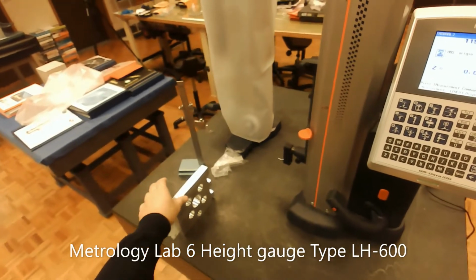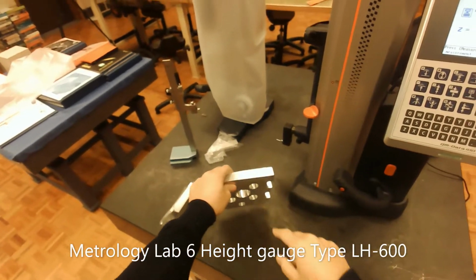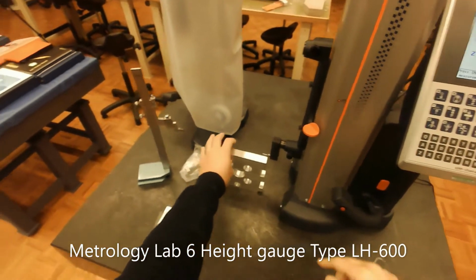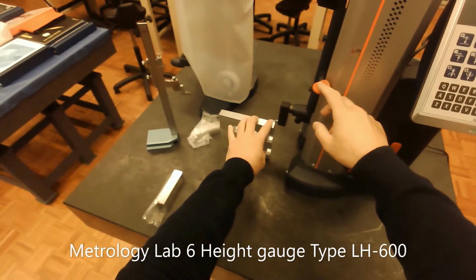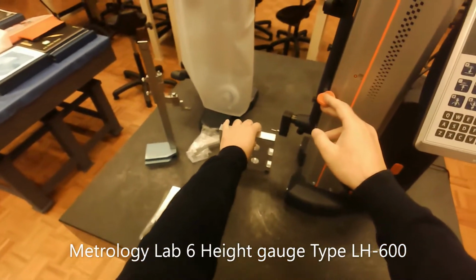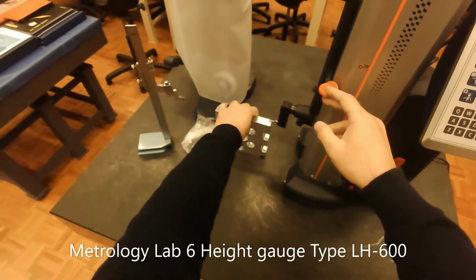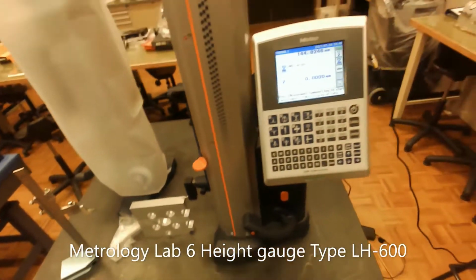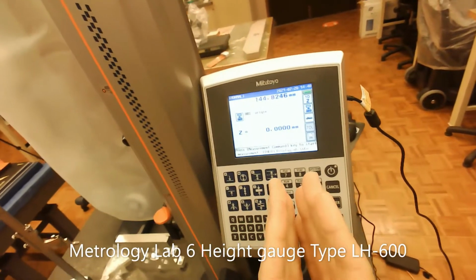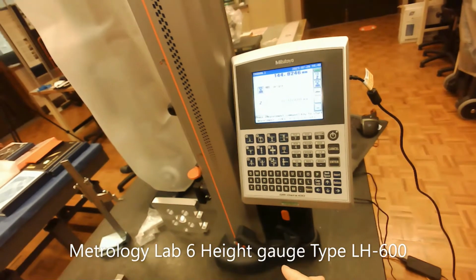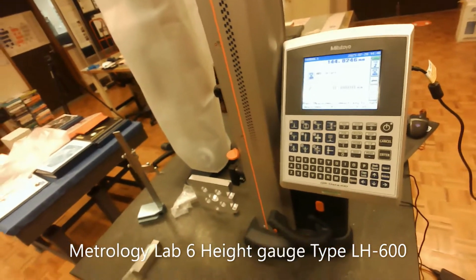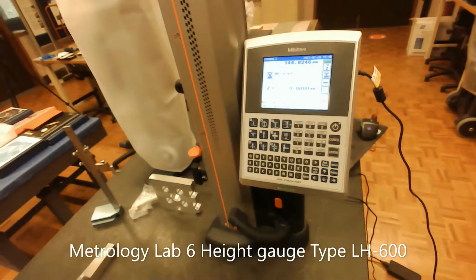My first test is going to be checking the height of that surface. I'm going to put it somewhere where the probe is going to touch it when it comes down. So I think that this will be a good position. It's reading as 144.83.